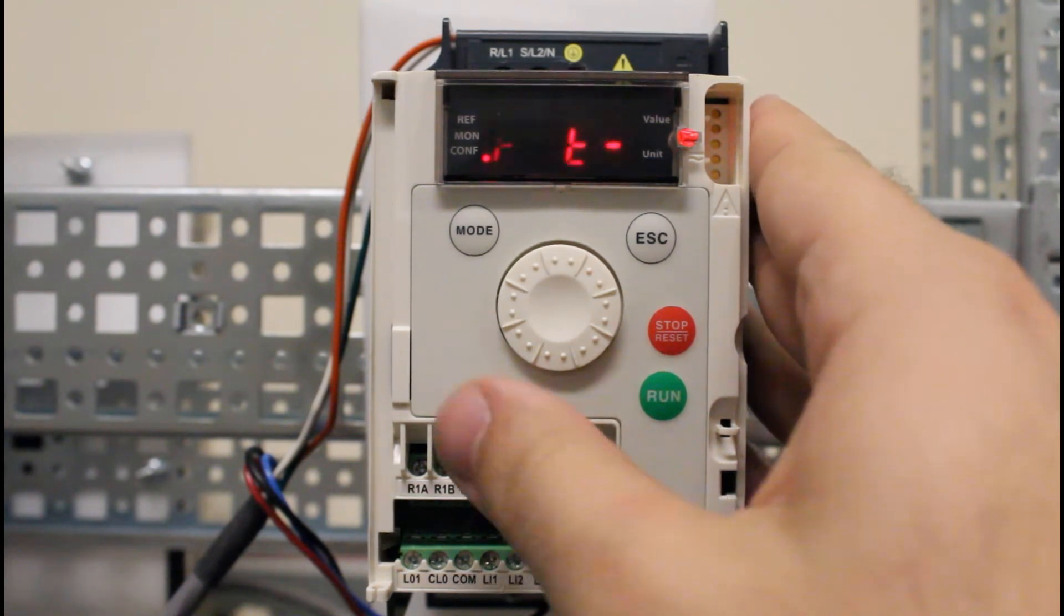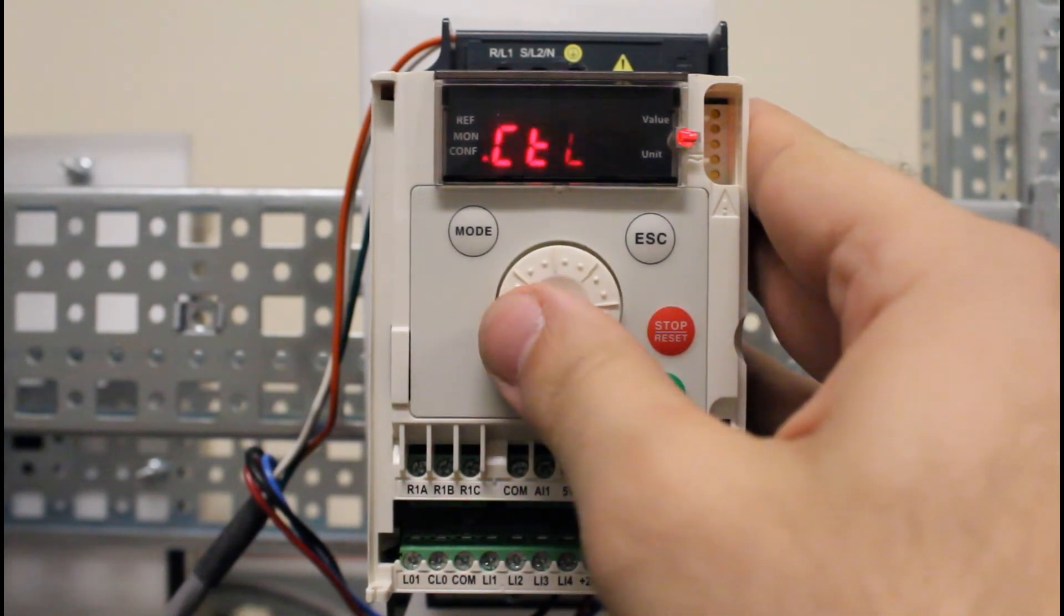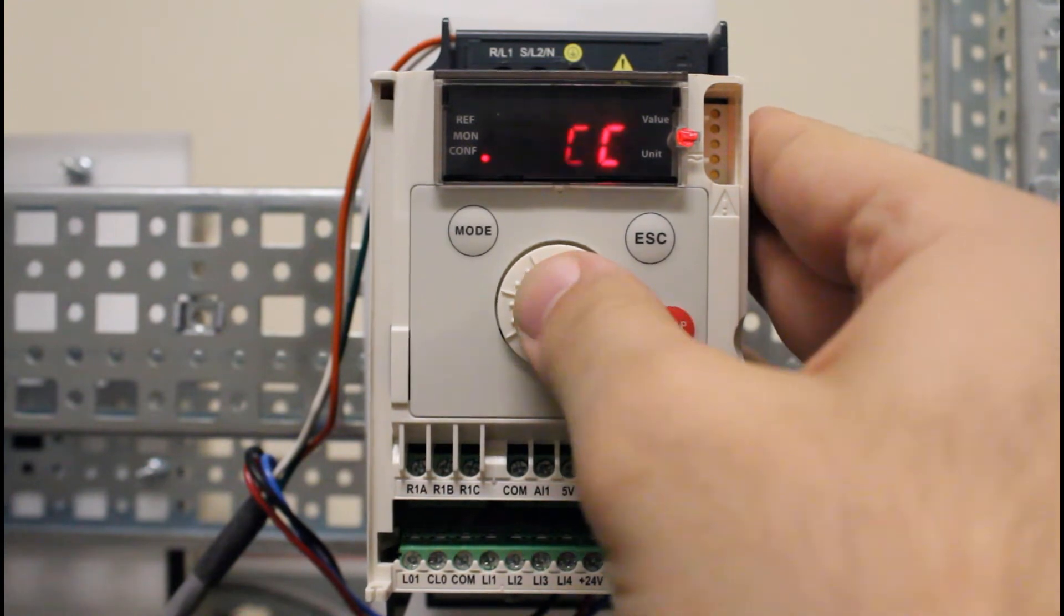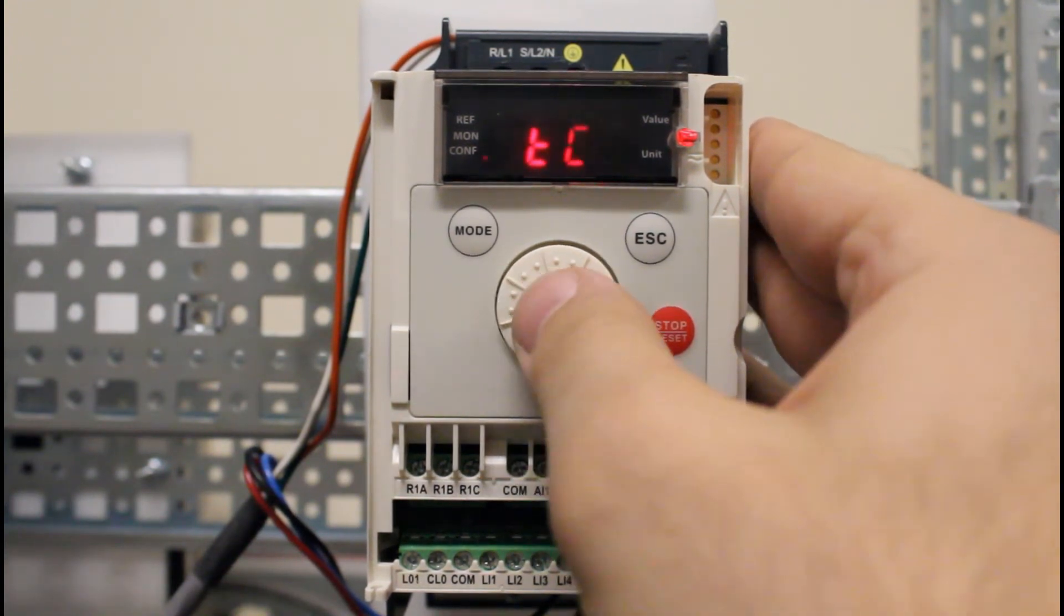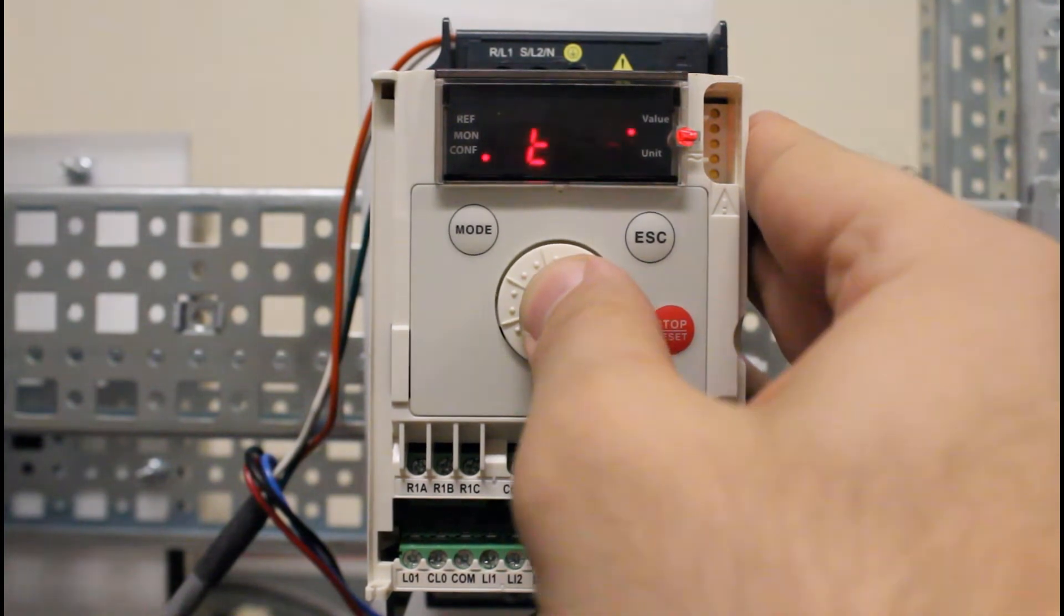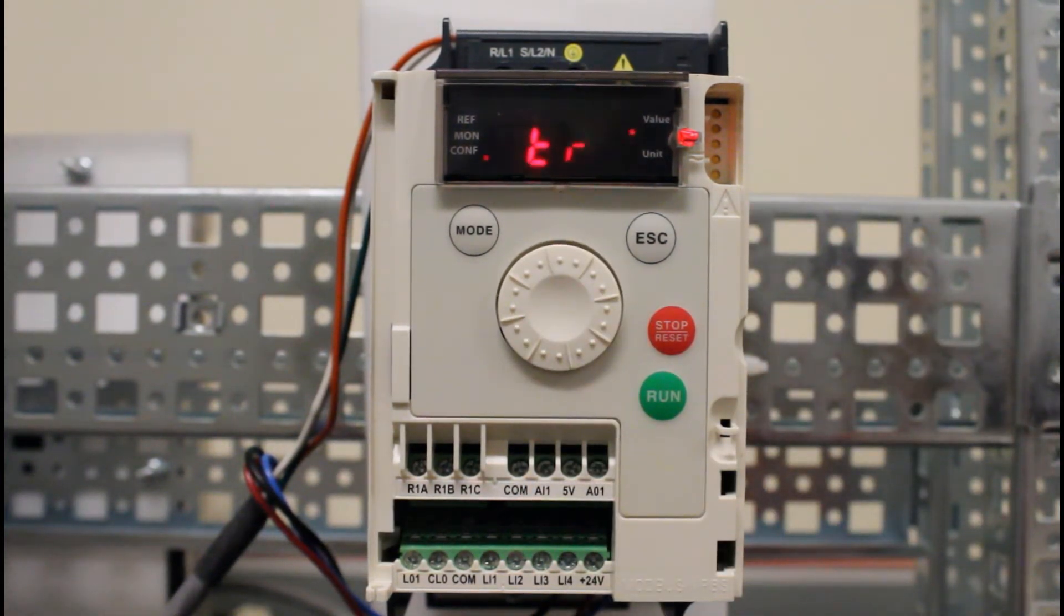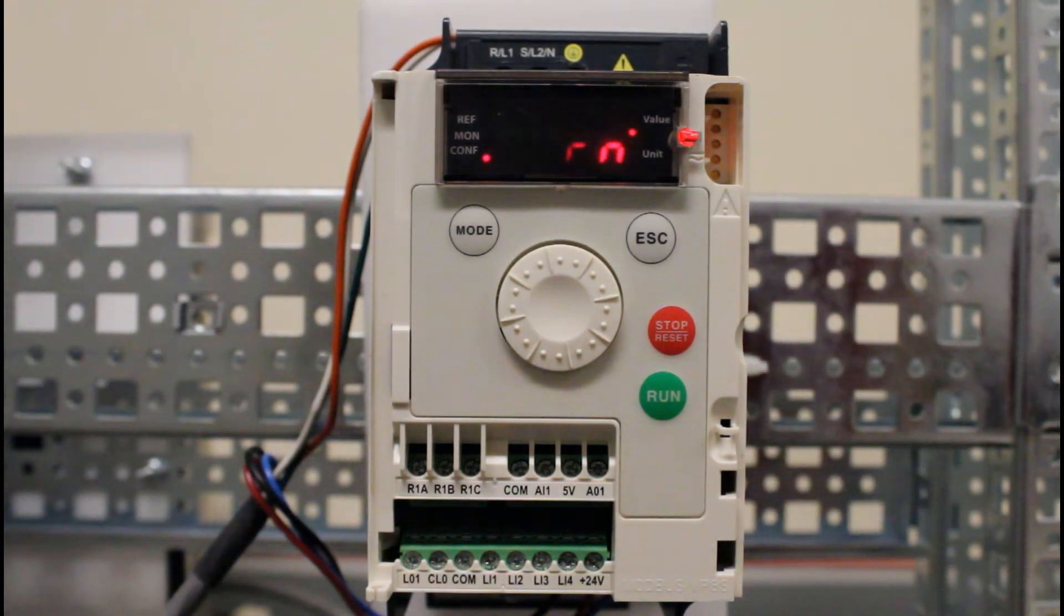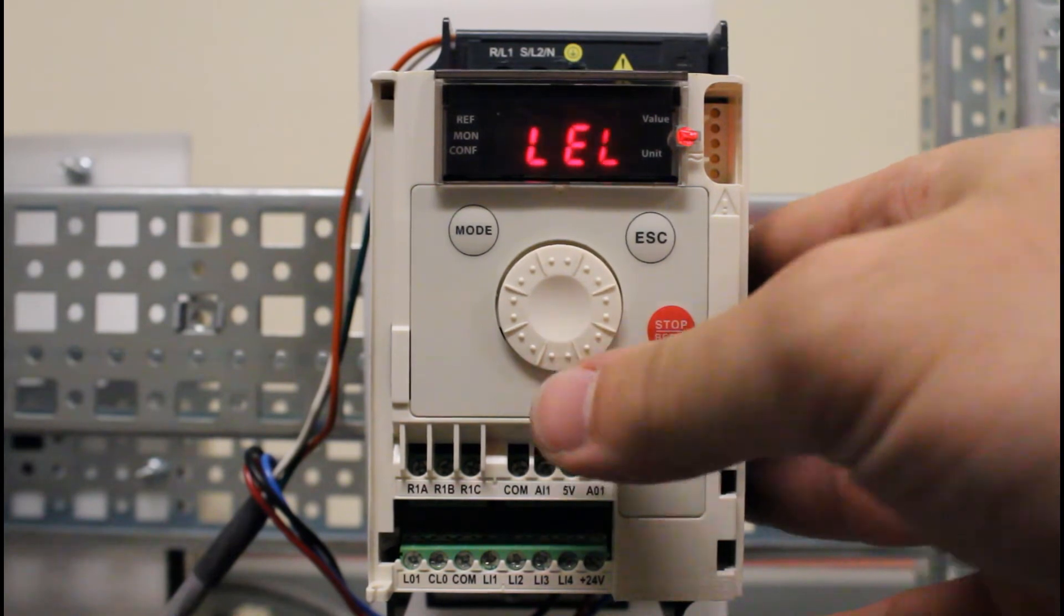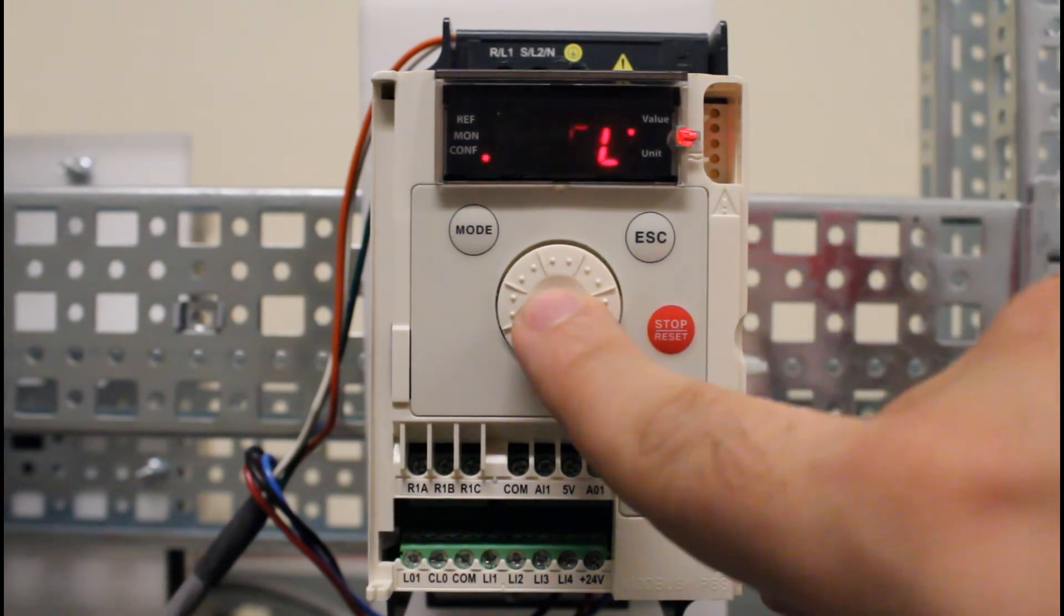Turn it counterclockwise to the IO menu, enter here, and then go down to TCT - this is your two-wire type parameter. From a default state it's on transition mode, which is not what we want. You want to be on level mode LEL, so you want to set this.